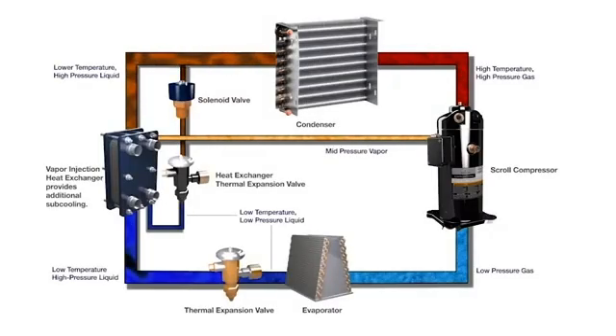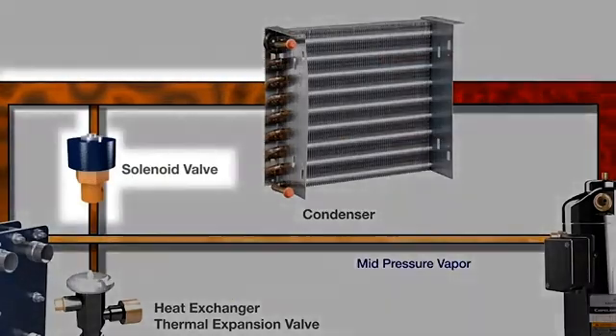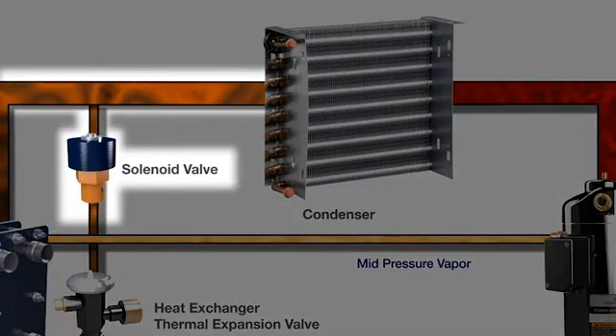For applications requiring maximum capacity at lower set points without adding more or larger compressors, Emerson offers a vapor injection system. It diverts a small amount of liquid refrigerant away from the main circuit, just after the condenser.